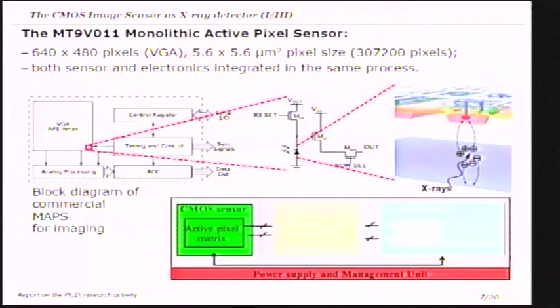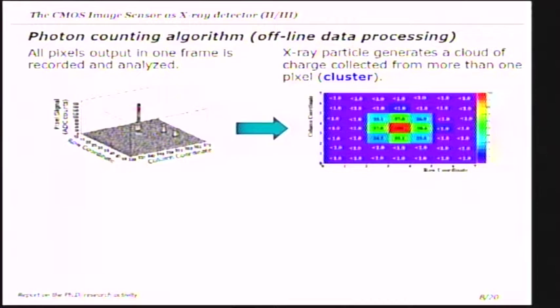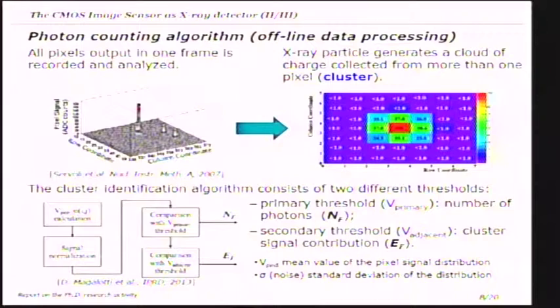I characterized the sensor, which consists of 300,000 pixels — each pixel was analyzed. When the sensor is exposed to x-ray photons, the x-ray photons interact with the sensor and generate a cloud of charge. This cloud of charge is collected by more than one pixel. The central pixel of the cluster is the seed and collects the higher value of the photon energy, while the surrounding pixels collect a fraction of the total photon energy.